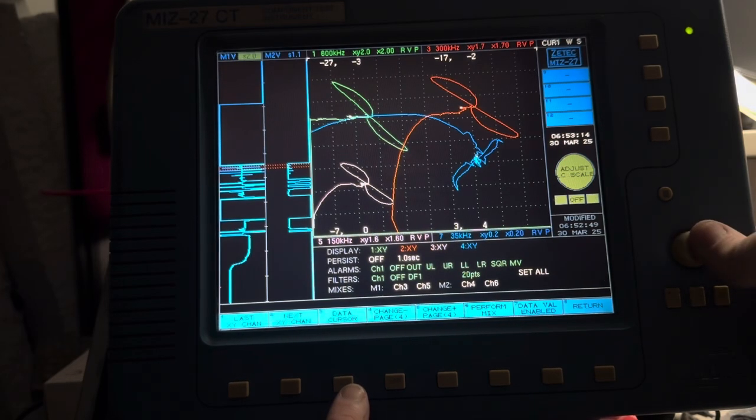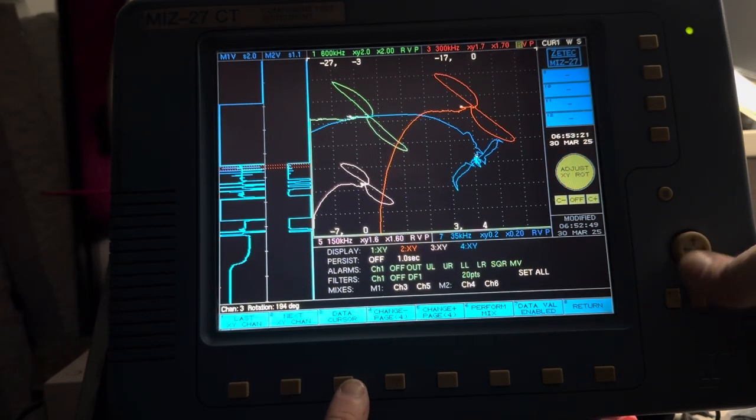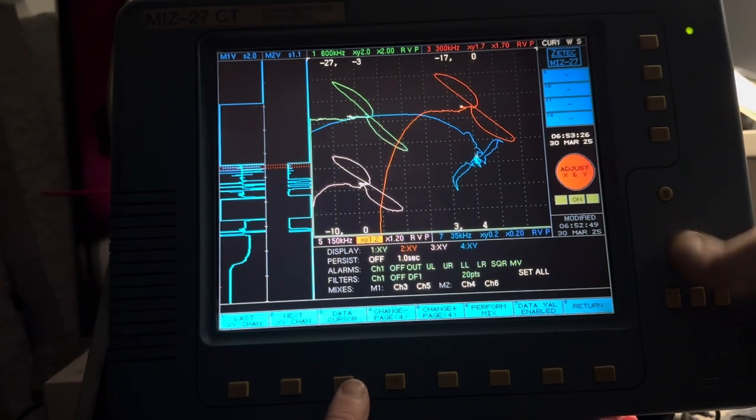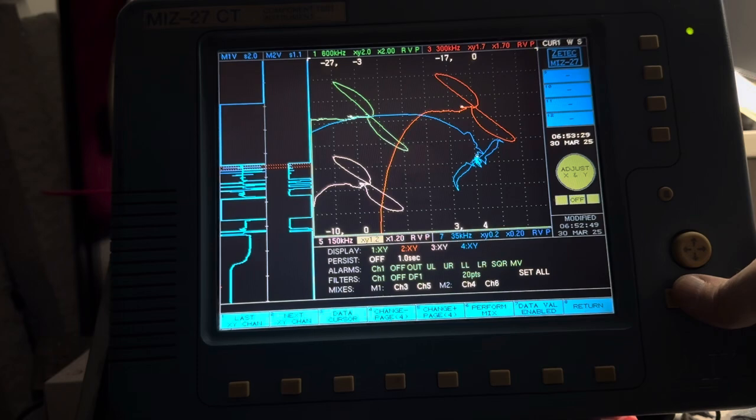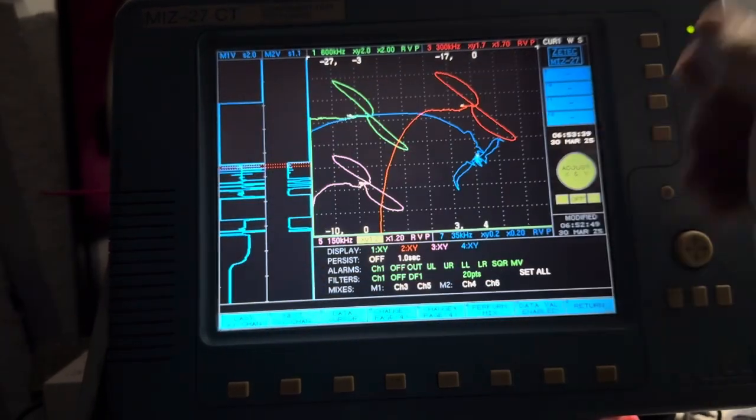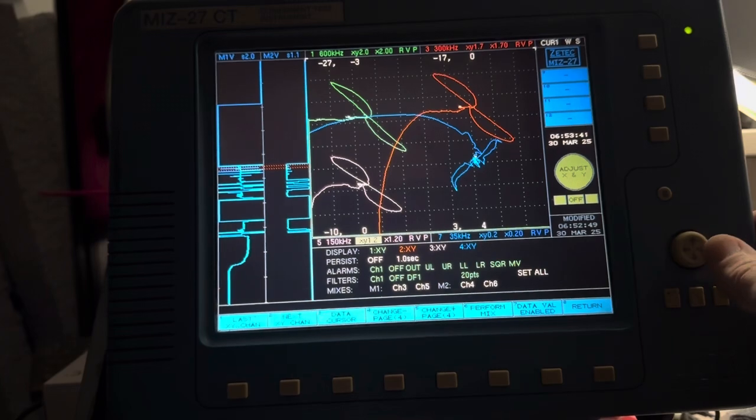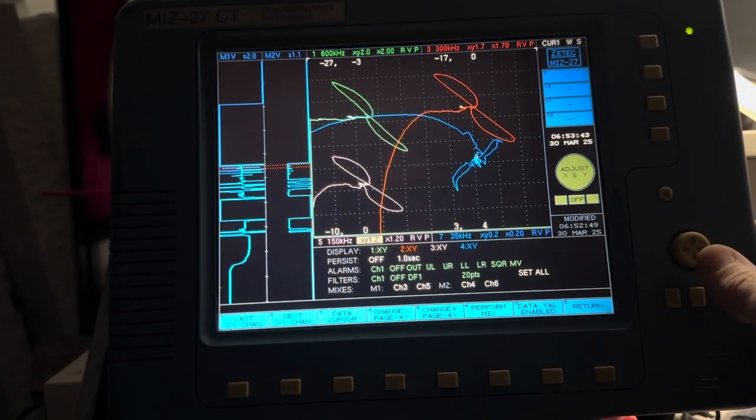And I want all of these channels to have the 100% flaw calibrated about the same phase and the same amplitude. Make that one a little bit bigger. What the data evaluators are really looking at is how the signal changes when you change through the different frequencies. So you're looking for phase rotation and you're looking for amplitude variations. If your flaw is getting bigger, there's going to be an amplitude change, larger. If your depth changes, you're going to get a phase change.